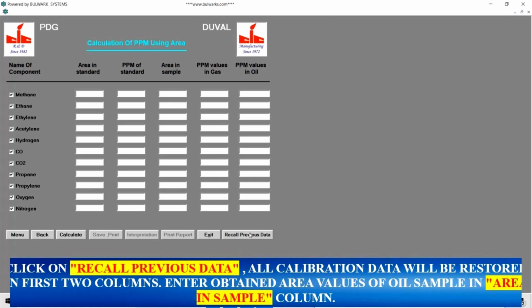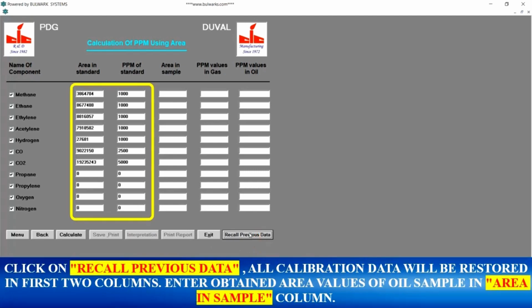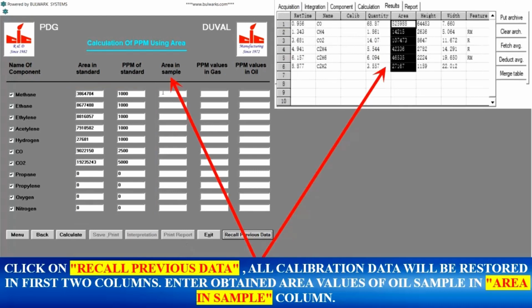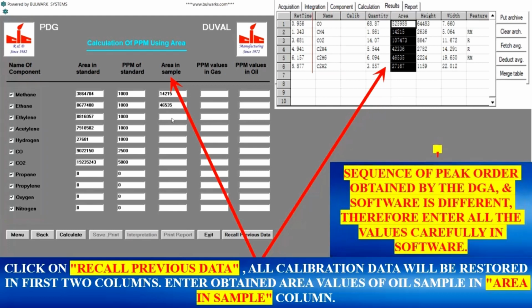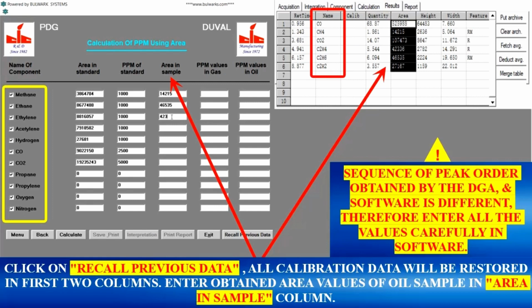Click on Recall Previous Data, all calibration data will be restored in the first two columns, as per previous calibration. Enter obtained area values of the oil sample in the area in sample column. Put 0 if the component is not detected by the system. The sequence of peak order obtained by the DGA and the software is different, therefore enter all the values carefully in the software.